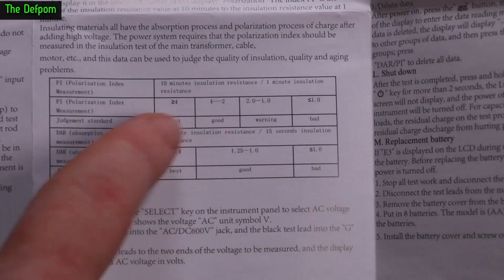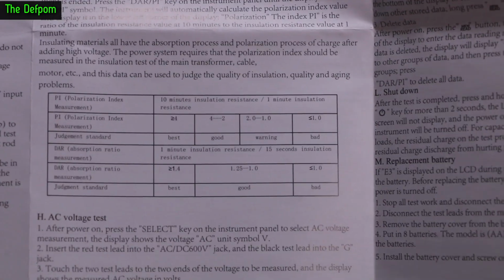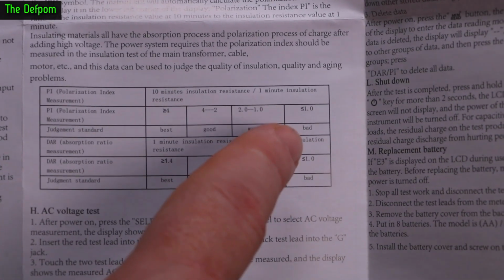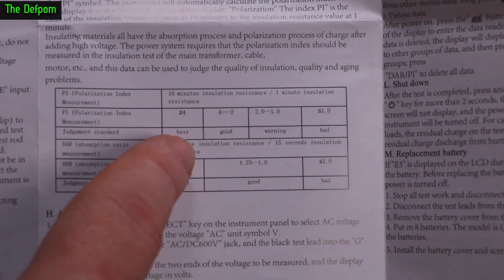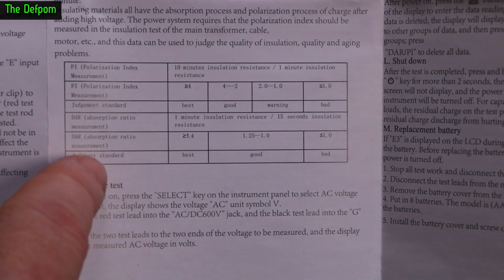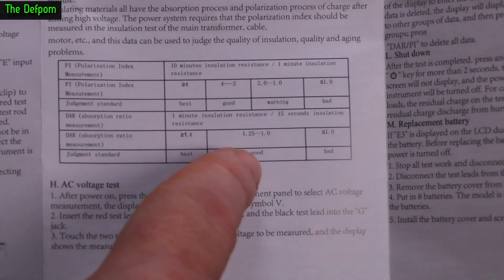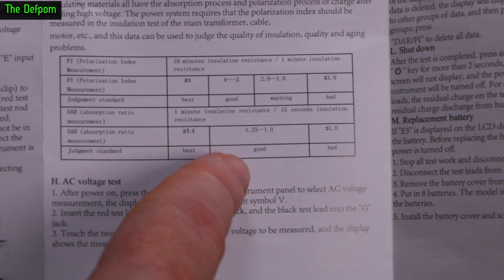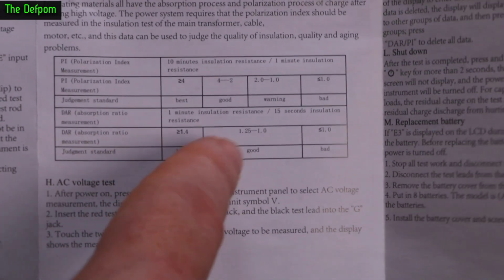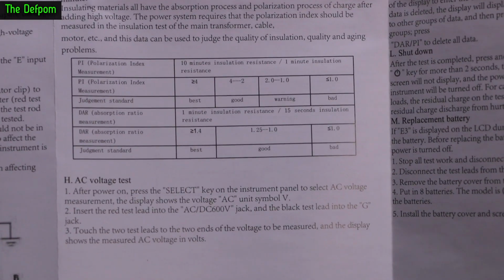Alright, so these are just examples here of what it considers to be a bad problem. Like if you've got less than 1, then you've got a problem. But you want to be higher, that's better, basically. The same for DAR as well. That's a 1 minute test, which we did before. We got 1.24, so that's towards the top end. So that's a good DAR reading.